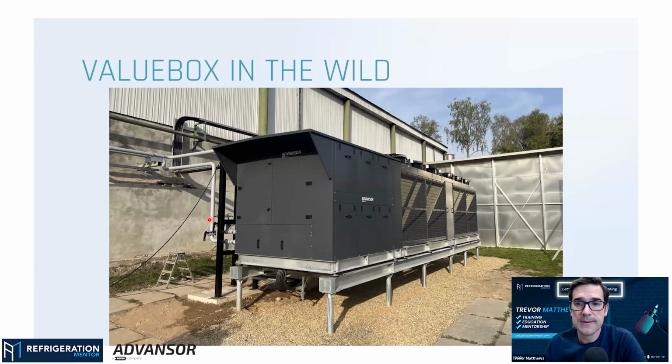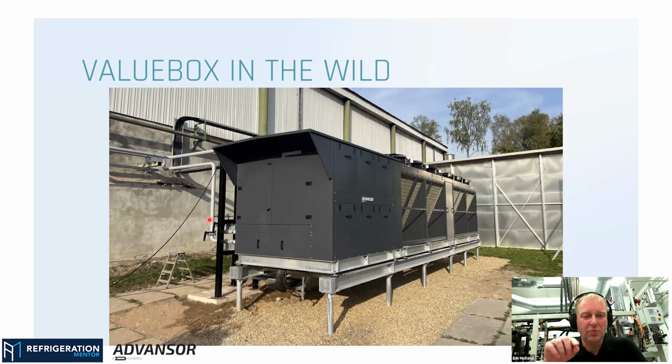I don't know what it is, but yeah, in that range, because in this case we have a really high evaporation temperature from the evaporators. We are up at like +10, +15 in evaporation temperature, and so we don't have any need for this MT stage anymore, because we're not operating in that range anymore. We're operating at a much higher range. So if you look at the P&ID where you have your MT and your IT and your LT compressors, you will see on a P&ID for this system, you will only have your IT, your parallel compressors. So that's a little bit of a special way to do this, but it works really good.